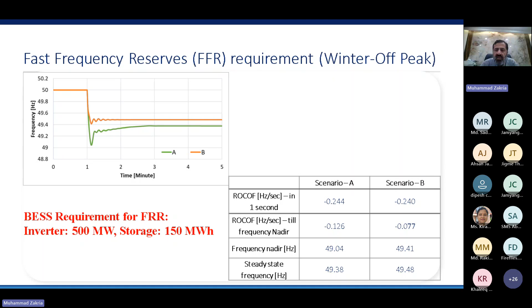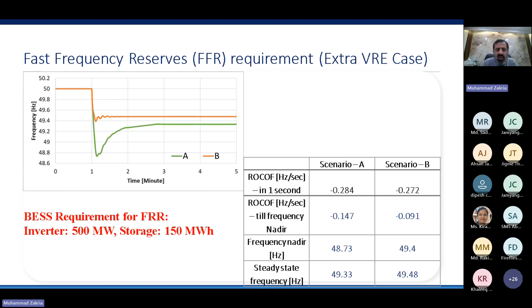Again, if frequency goes to 48.8, it depends on the ROCOF, the rate of change of frequency. In high demand season, the rate of change of frequency is lower. So this 48.8 will come to 49.4 with this 500 megawatt addition. These are the studies we conducted at ISMO at our own level and submitted to ADB.